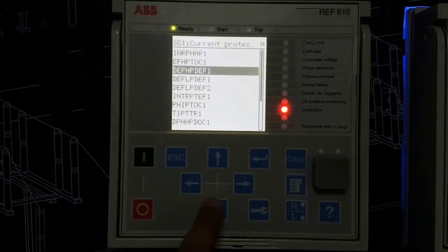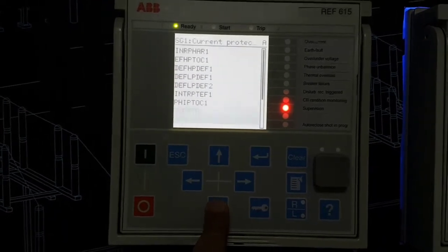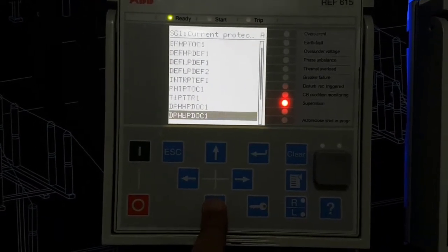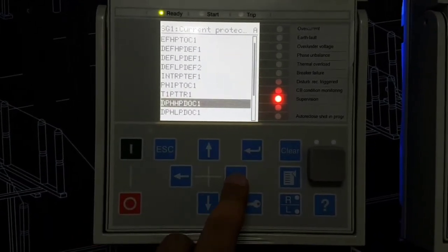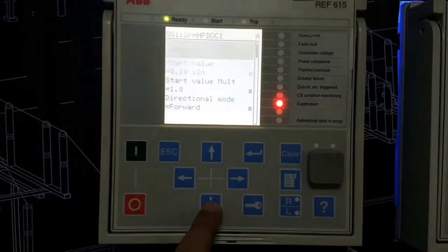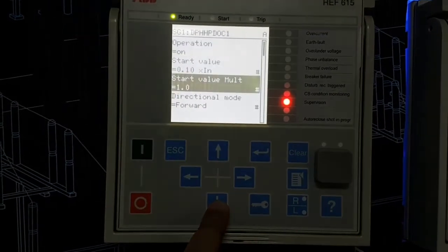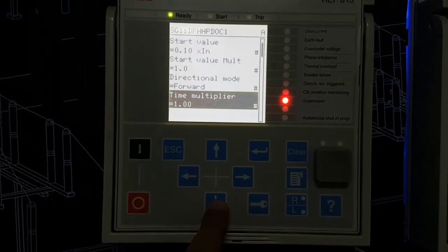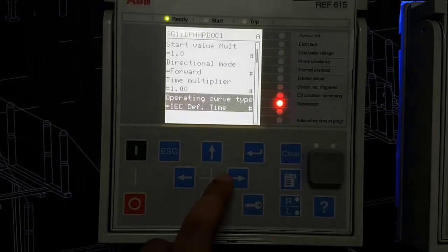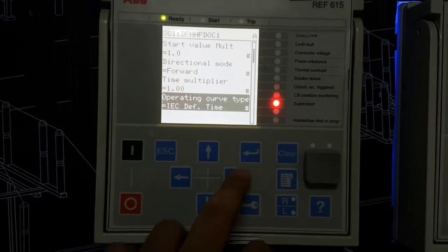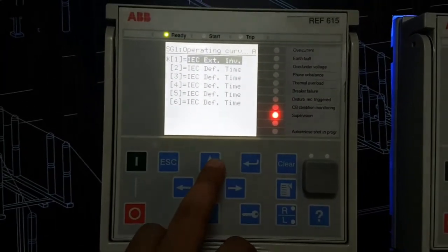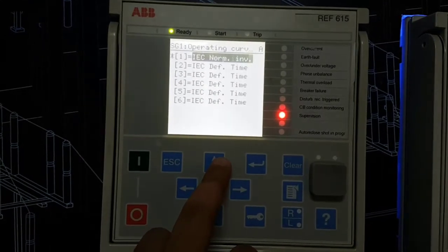Let's go back. Then you can see the directional overcurrent. Here the directional mode is forward and the operating curve type is IEC definite time. You can change it to IEC very inverse, IEC normal inverse, programmable.